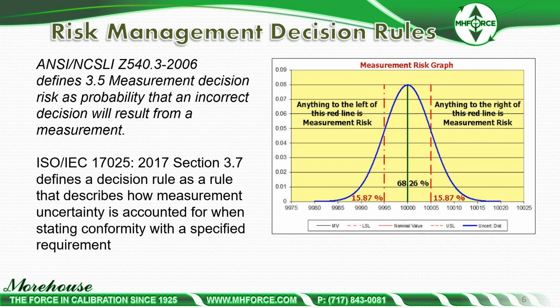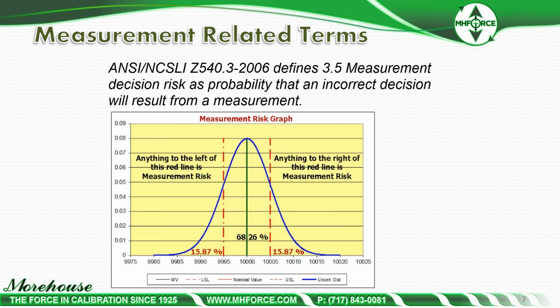And when we start talking about risk specifically, what are we talking about? We're talking about measurement decision risk as a probability that an incorrect decision will result from a measurement. Here's a nice graph. This is one standard deviation here on the graph, and anything to the left of the red line or to the right of the red line is risk. So ISO 17025 defines a decision rule as a rule that describes how measurement uncertainty is accounted for when stating conformity. That's essentially what we're doing here.